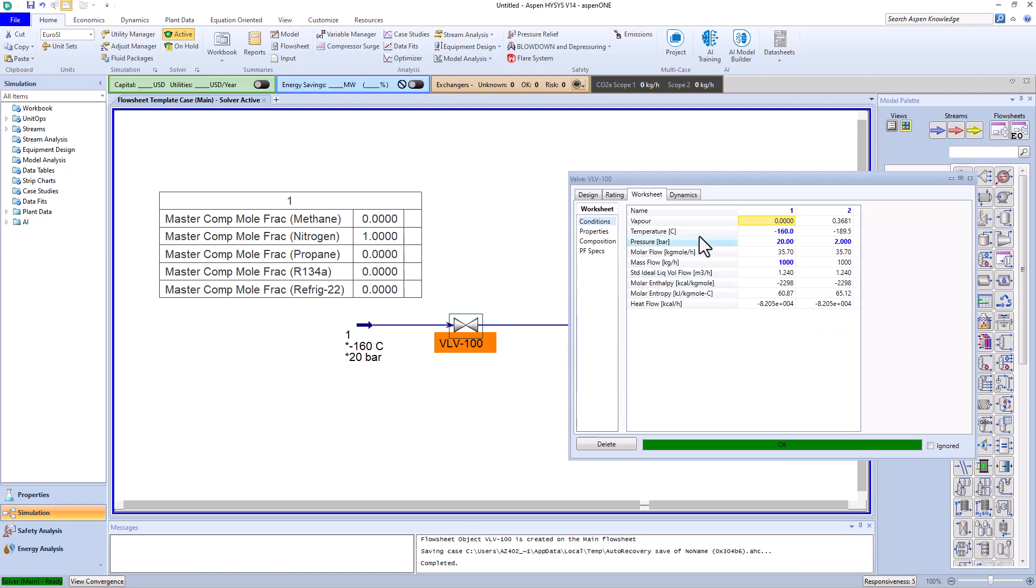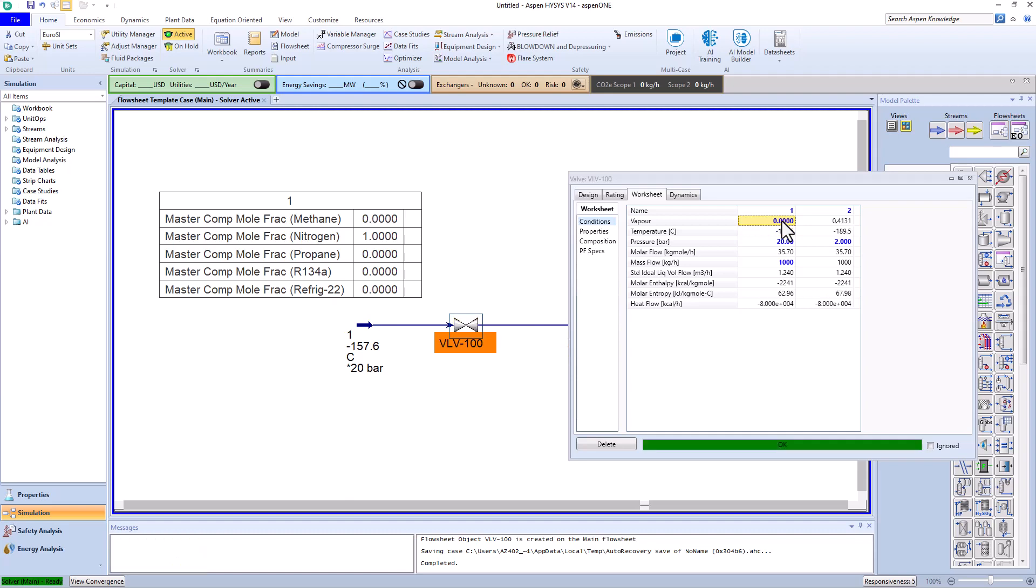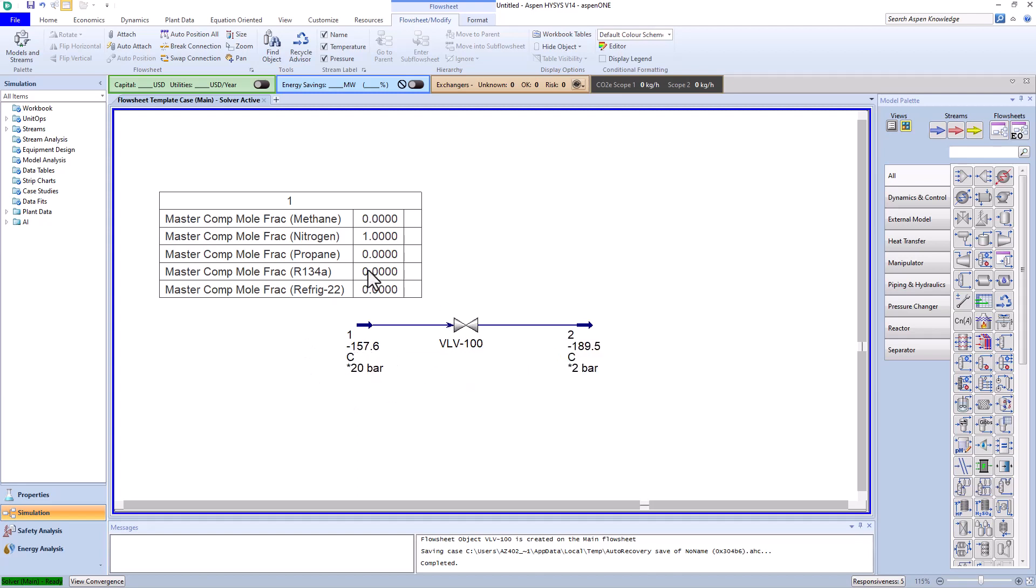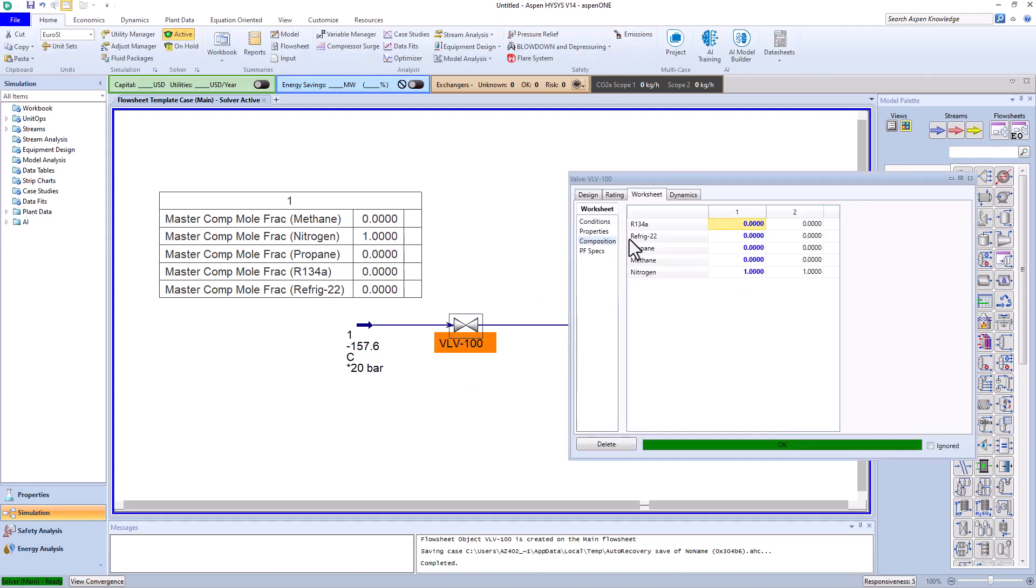So remember that the closer the flow is to liquid before the pressure reducer, the stronger the Joule-Thomson effect will be. Now let's focus on entirely saturated liquid and set the vapor fraction to zero instead of temperature.